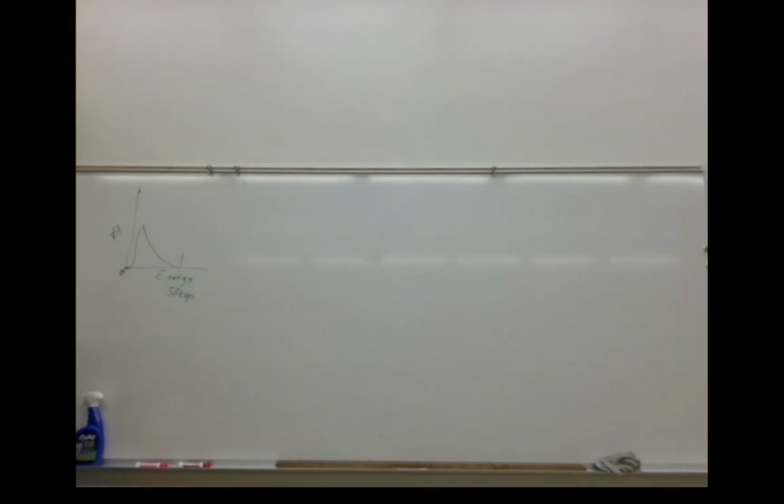I also put a couple of videos of the Biomed guy from ETMC, now UT. It was ETMC at the time. A Biomed guy took the collimator housing off and he made some exposures. When he made the exposures, you could actually see the electrons jump from cathode to anode. It just looked like a flash, right? Your patient sometimes will say, I know the X-ray took because I saw the flash, but they can't see the flash. There's too much stuff in the way. So it's got to go through something to get out of the housing. That port is also going to remove some of those low energy X-ray photons, and it looks something like that.